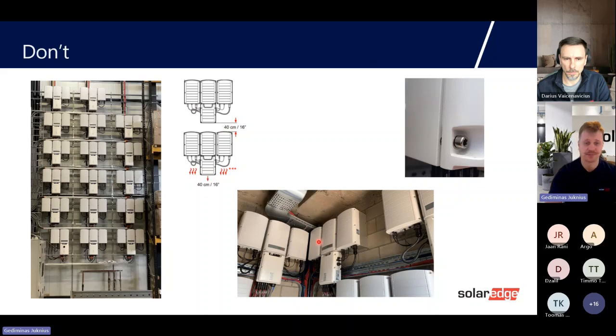Here, sometimes in the small cabinets, we see that inverters are pushed because you have no space. Guys, if you ever get into a small room full of inverters running in the middle of the summer, you will notice that it's like a sauna and you need to bring cold beer, because inverters are spreading a lot of heat from the grill when the production is at the maximum.